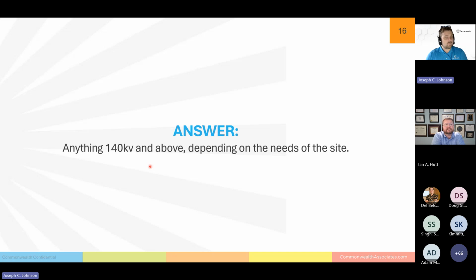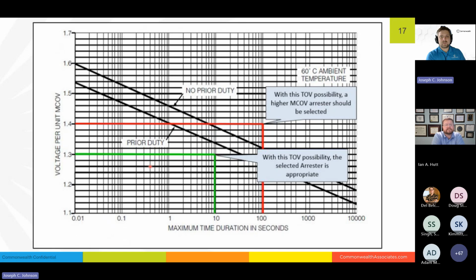140 is just above that, but I've seen many cases where 160, even 180 would be used in this case. These aren't necessarily standard classes, by the way. It was just a thought exercise, but these arrestors can be sized greater. They just have higher residual voltages, which we'll also go into, and the consideration there of how much protection margin you are sacrificing. At the same time, the benefit is you don't need as much energy rating because they're not going to operate as regularly during TOV events. So, speaking of TOV, this is a slide with the TOV curve, and I'll pass it back to Ian to explain this. Yeah, thank you, Joe.